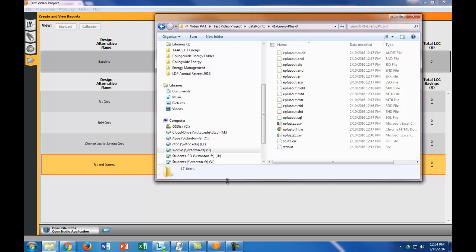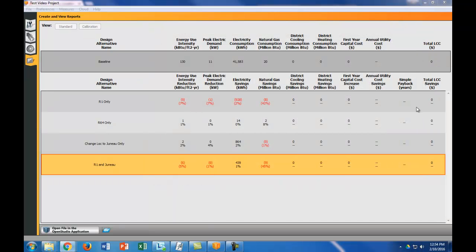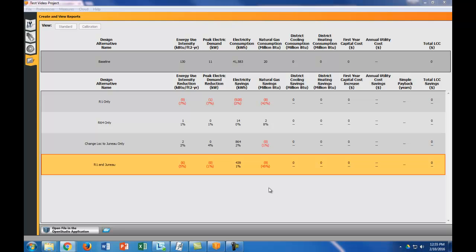So that's how you run the parametric analysis tool. And you can see that there's a lot of stuff you can do here. Not only with energy conservation measures, but if you have a building designed in your, let's say you have a big box store or a retail outlet and you want to put it all over the country and it's the same design, you could test all those different locations to see which would perform well and which would not perform well. And you could modify different locations for different insulation values as well. The other thing that we didn't really cover is you can even put in how much these measures would cost. So for example, R64 is a good example. If we really bulked up the exterior walls, we could put in how much basically it would cost to put that in, so the capital cost increase. And then energy plus would calculate the utility cost savings and the simple payback and the life cycle cost savings. So it's a pretty powerful tool and gives you a lot of different tools at your disposal. All right. Hopefully that helps. Thanks for watching.